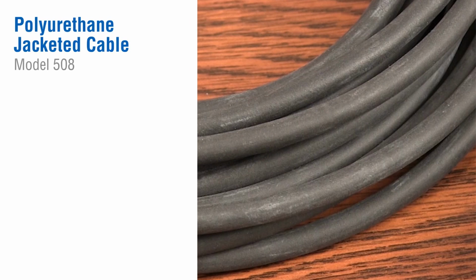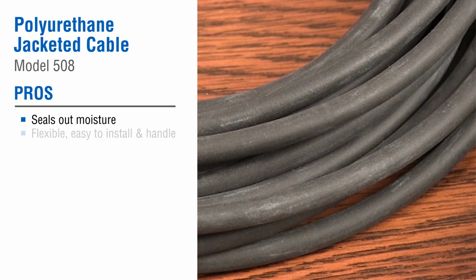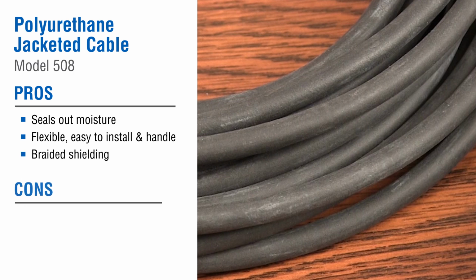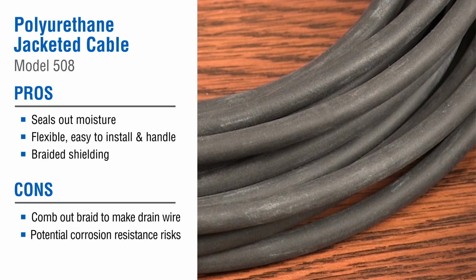Polyurethane jacketed cables, such as our cable type 508, are great for sealing out moisture. They are flexible and easy to work with. They have a braided shield, so installers must comb out the braid to create a drain wire. We will cover this in a moment. It's best for you and your applications engineer to check chemical compatibility if there are any concerns about chemical exposure.